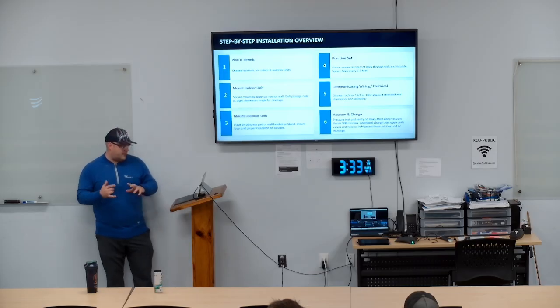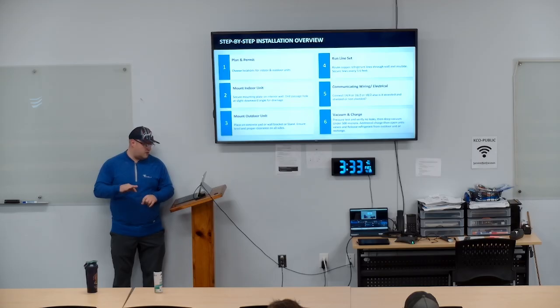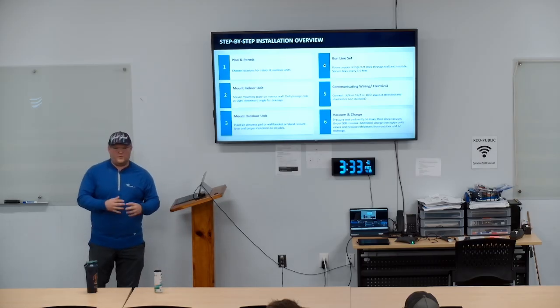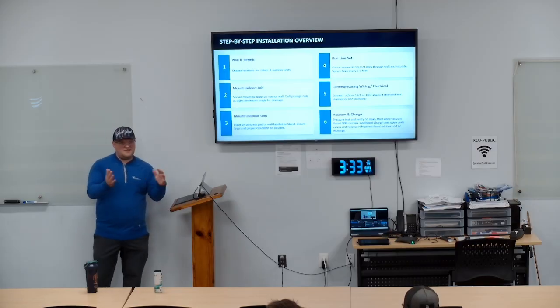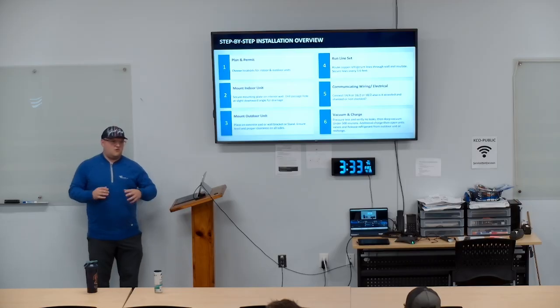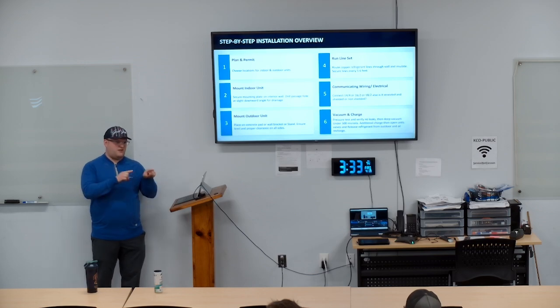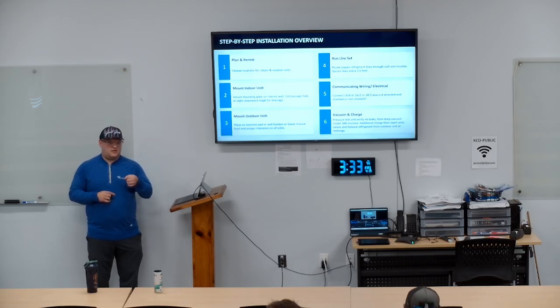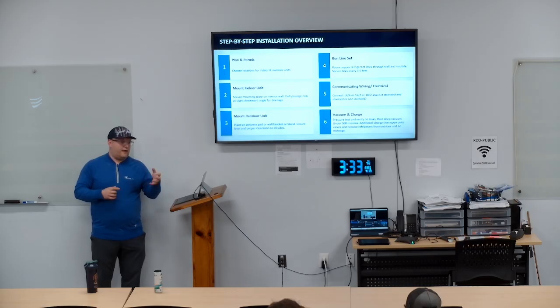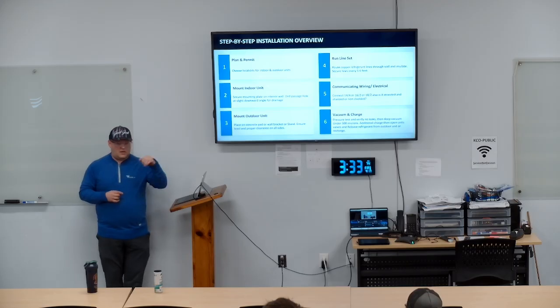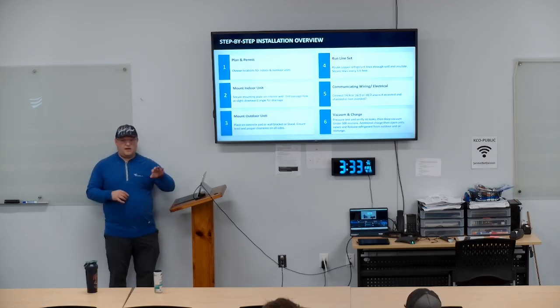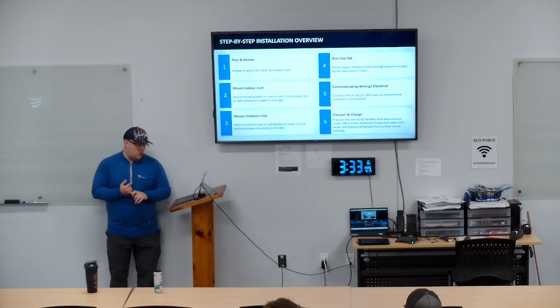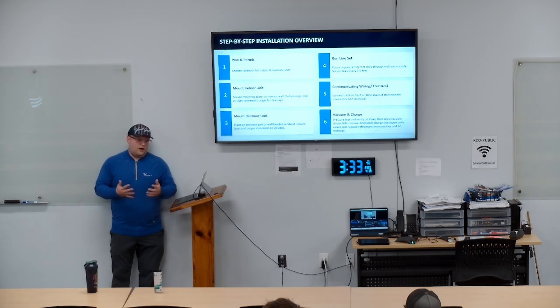Communication wiring, electrical, we were talking about that. 14-4, 16-2, 18-2. Those are the main ones I see. 14-4 is always a weird one. Everyone wants to know, does the electrician run it? Do we run it? Normally, on a 14-4, we're running it. The electrician is bringing power into the outdoor unit. We're running a 14-4, that black wire that we run. That sheath around it is rated for outdoor, okay? So we can run it in, tie it in, it's just simple. They'll land L1, L2, ground, and then we would technically call our 14-4 wire a communicating wire.